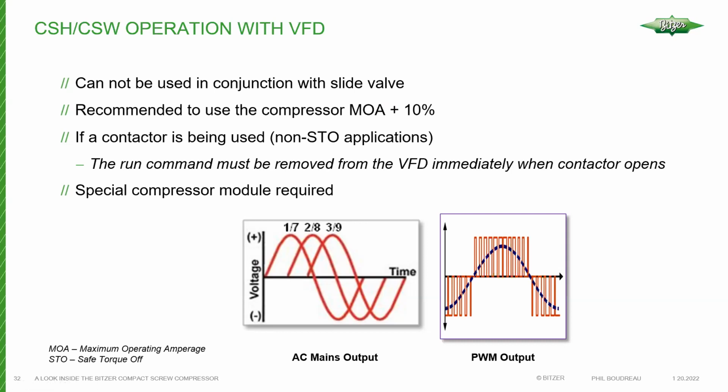that compressor can draw. So it's tied to, you could say, the maximum power input to that motor as well. That motor can only do so much. If you push it too far, it's going to overload. So that point at which the motor is fully loaded up would be considered like the MOA. That's a common term used overseas. In other countries, here in North America, MCC is more common. MCC and MOA are, I would say, fairly similar in terms of the actual value. But we use the MOA regardless for sizing compressors, or VFDs rather.